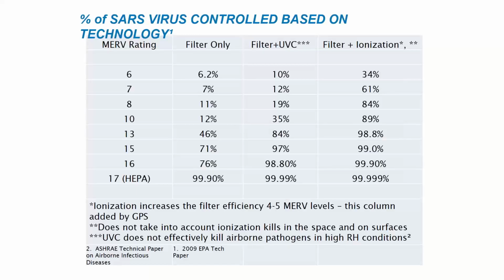All right, we talked before about, if I take 2 Merv 8 filters and add them together, do I get a Merv 16? No, you don't - you still get Merv 8. And I mentioned there's ways to make your Merv filter behave better and get more cumulative effect.